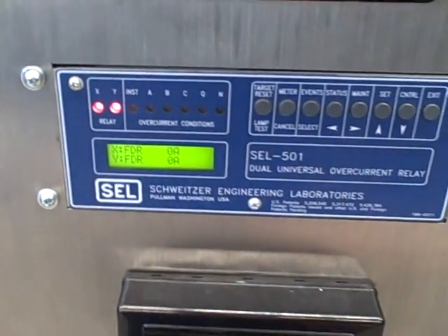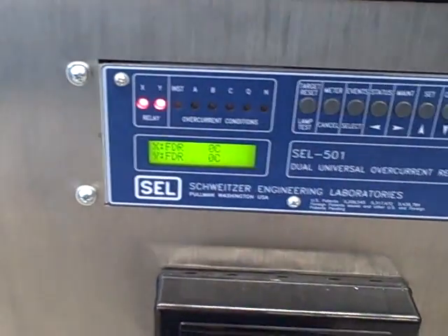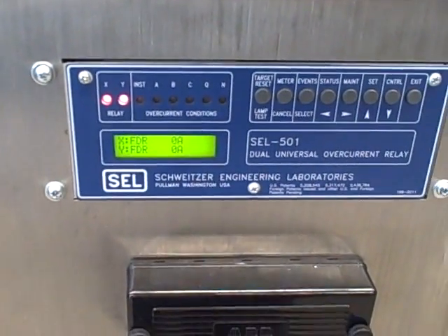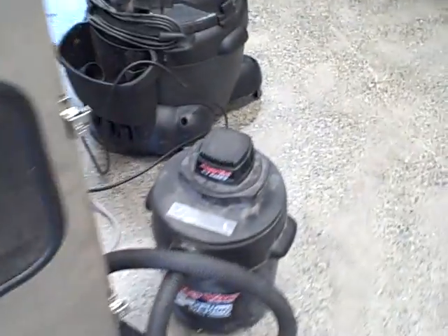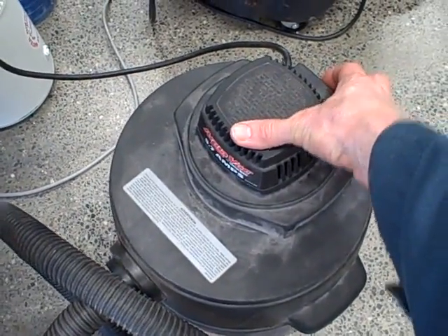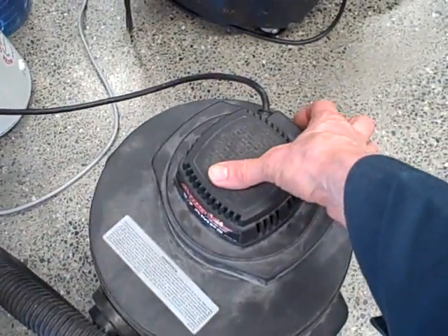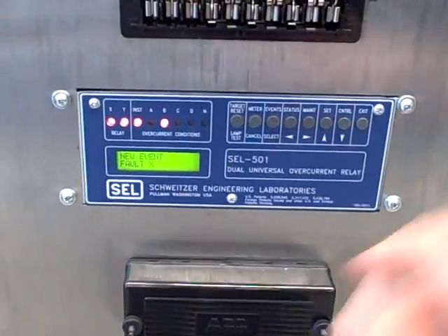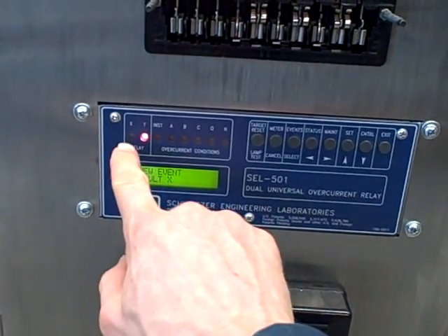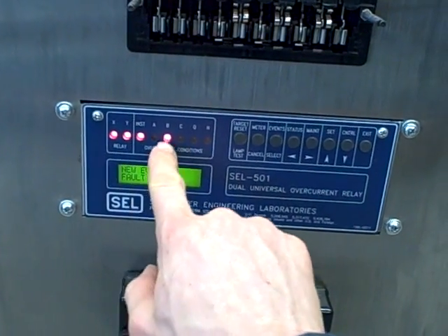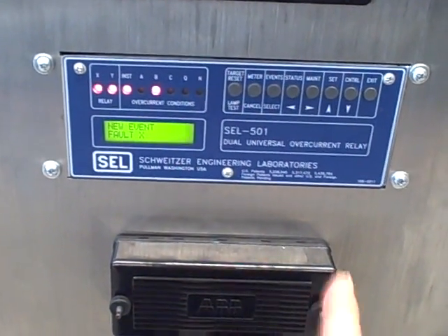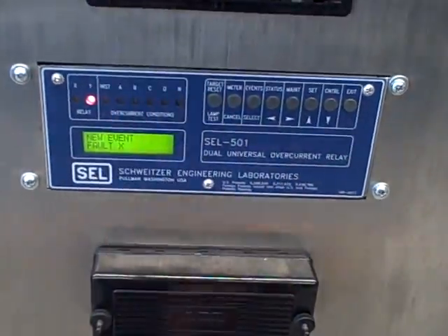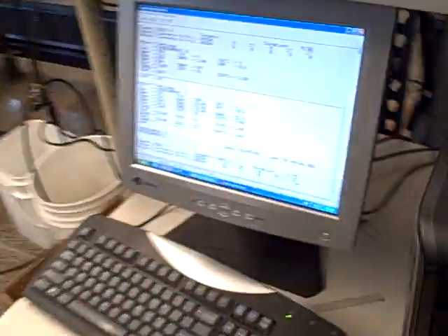At this point, this should be sensitive enough on the instantaneous over current element to trip on phase B if I turn on the vacuum cleaner. So let's see what happens. Sure enough, I turn it on. You can hear the thunk of the circuit breakers opening, tripping. If I look at the front panel of the relay, I see I've got targets here indicating a trip on the X relay, instantaneous phase B. Remember, we're only using phase B on this three-phase relay, which is why we only see a trip there.